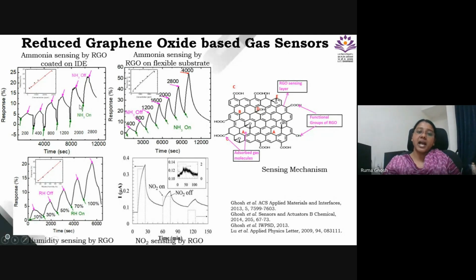Another problem, not listed in the parameters: if the device has to be repeatable, each time the gas is desorbed from the sensor, the resistance should reach back to this baseline, to zero. But look at this, it is over-recovering, going till negative. In the second graph, it is moving up. In technological terms, this is called baseline drift.